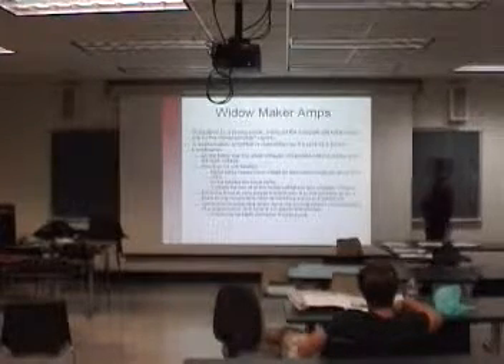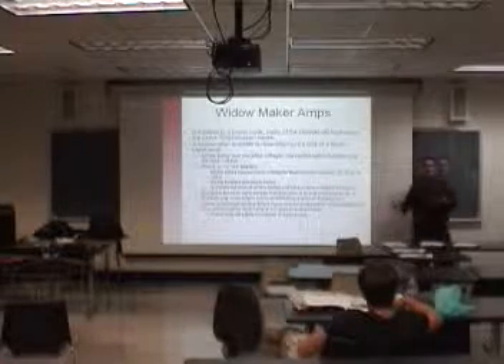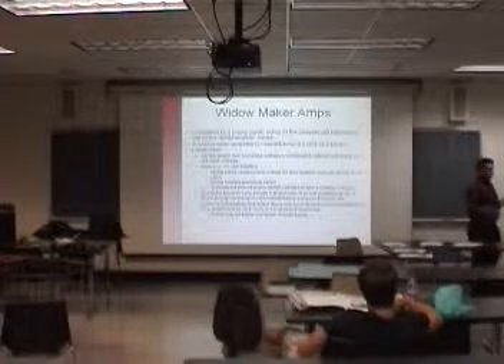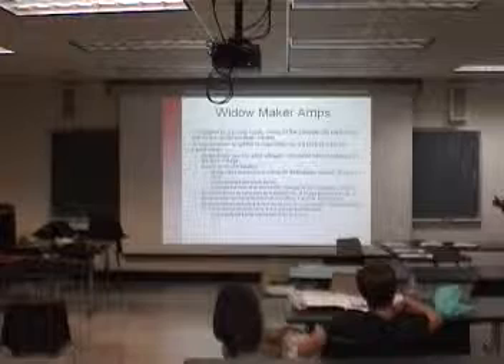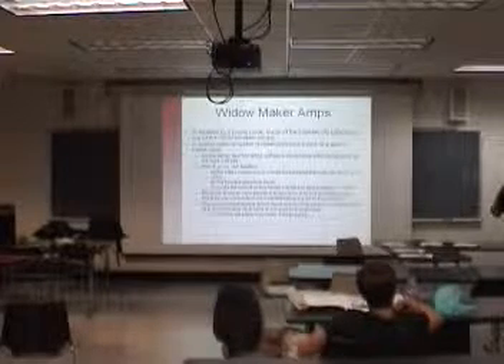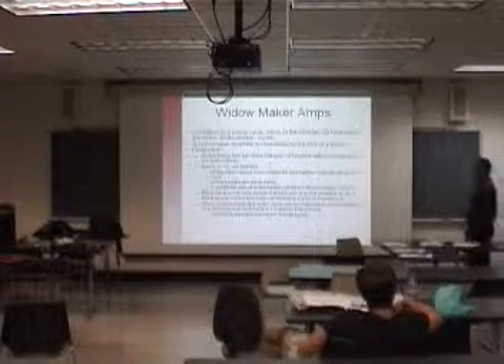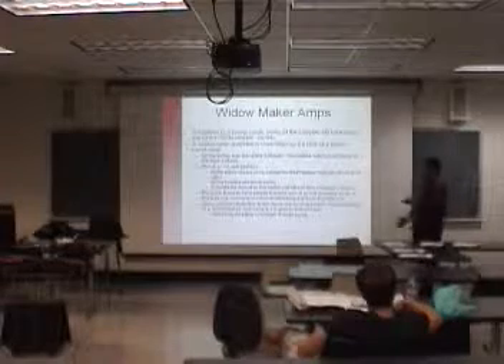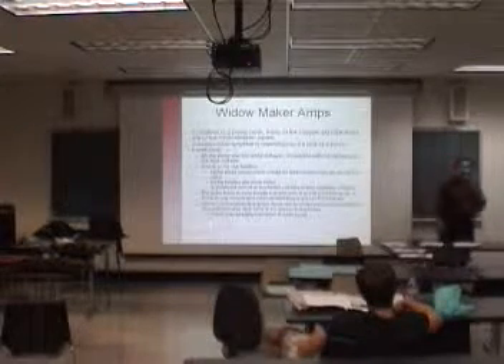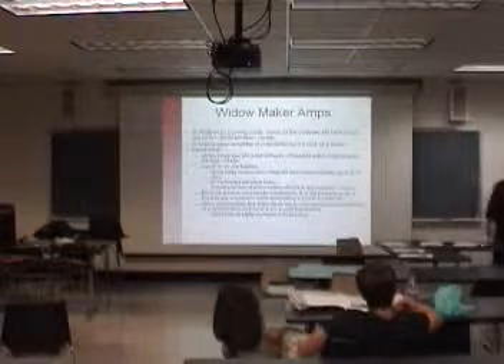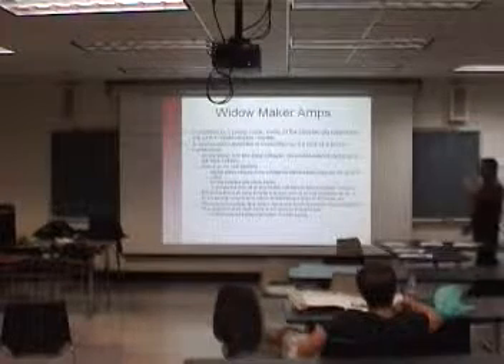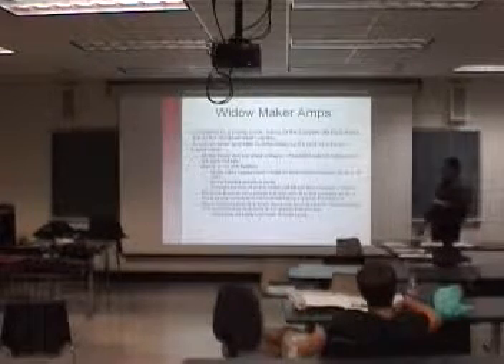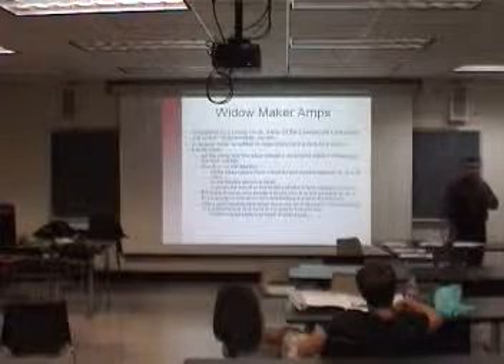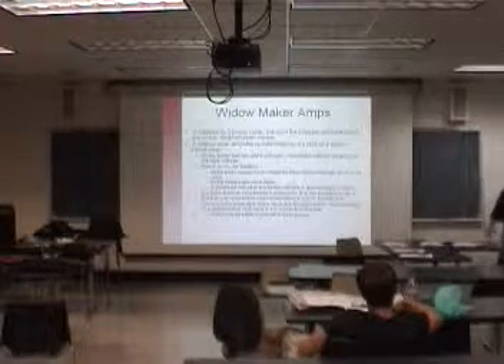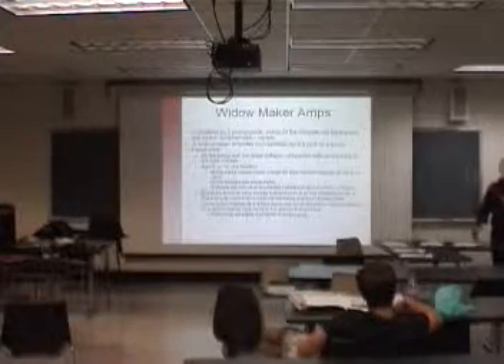Now, since you don't have a power transformer, you can't convert them to 3-prong. Basically the way they work is neutral is tied to chassis, period, end of story. The only way to fix that is to install your own transformer. So you get an isolation transformer - normally that just means a 1-to-1 transformer, but here you're talking a 1-to-1 power transformer with current, and then you can wire it to a 3-prong.